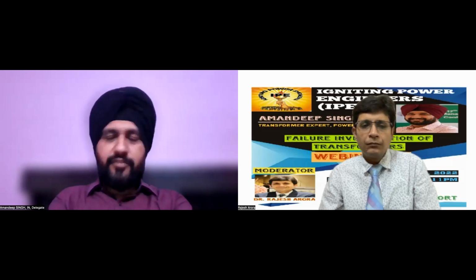Let us say there is a fault inside the transformer and the transformer tank ruptures. In that case, the oil inside the conservator, which would be around 5 to 10 kl on an average, would rush into the main tank, and this oil would ultimately get wasted. So the NRV works on a simple principle that whenever there is any sudden flow of oil to or from the conservator, it shuts off the supply. But if there is any slow flow, like normal breathing of the transformer, or normal operation, it is not cut off.